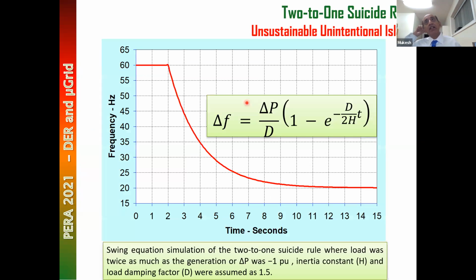Basically, if you look at the swing equation, this is just a simple simulation of the swing equation where the generation is reduced to half, the load is 1 per unit, and you use a damping of 1.5. If you do a simulation of the swing equation, you'll see the frequency will automatically drop so fast, within seconds, that your source will not be sustainable. This was good to show to my colleagues who are questioning the 2:1 rule, but you are all going to university and you know the swing equation very well.